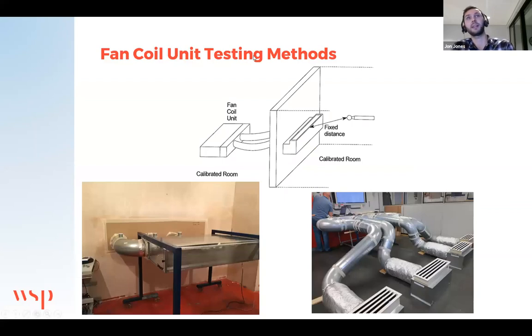Looking here at a testing setup, the way to do this would be to install a fan coil unit in one of the calibrated rooms in a test laboratory and measure the noise level in it. In this space, you'll get the casing inlet and the casing breakout noise to measure. Then at the termination point, you get the noise level from the outlet. From that, you can derive sound power levels for each of those, which is great. And that's exactly what we're looking for when we take information from mechanical services, building services engineers, and work through an acoustic assessment on that basis.